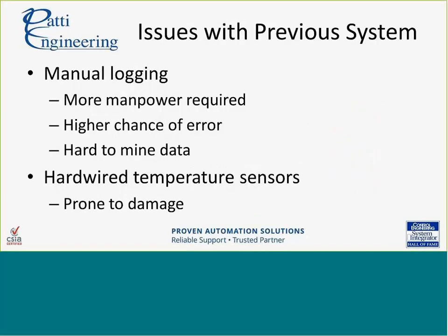Issues with their previous system. It was all manual. It was a hardwired system of temperature sensors throughout the plants. It required a lot of manpower to log the data and keep track of it. This opened up room for errors and mistyping or misplacing paperwork, and all the paperwork is certainly hard to go through and mine data when the SQF audit comes around or if a customer needs specific temperature data.